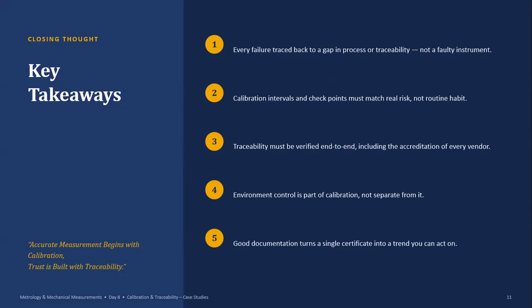Let us conclude today's session with five important key takeaways. First, measurement failures often originate from gaps in the calibration process or traceability chain rather than from a faulty instrument. The calibration intervals and verification points should reflect actual risk and operating conditions. Traceability must be verified from end to end, including the accreditation of calibration service providers. Environmental control is an integral part of reliable measurement. Good documentation transforms a calibration certificate from a static record into useful information for monitoring measurement drift.